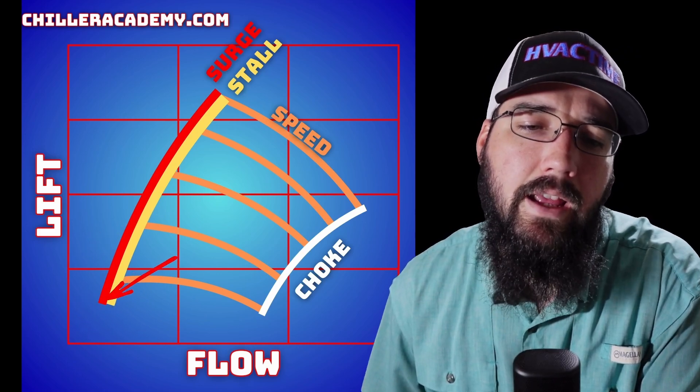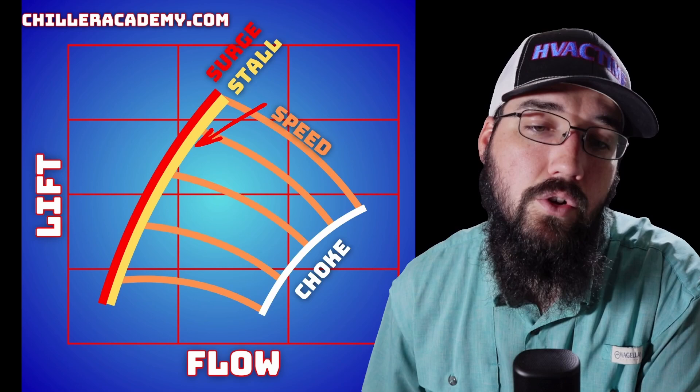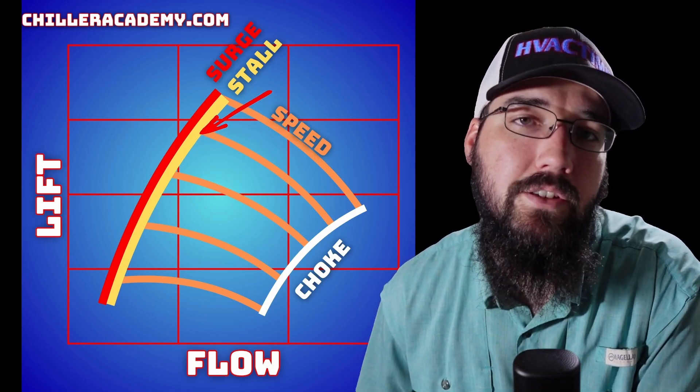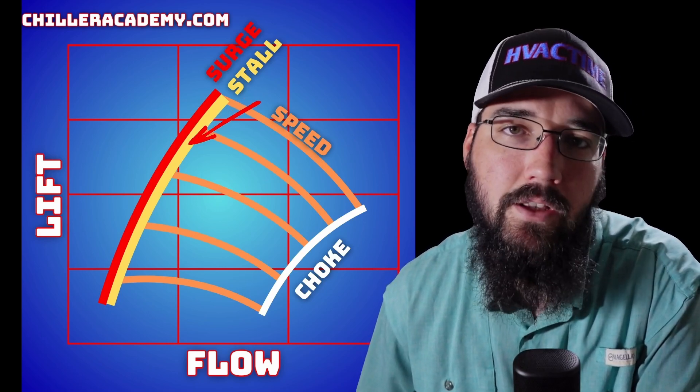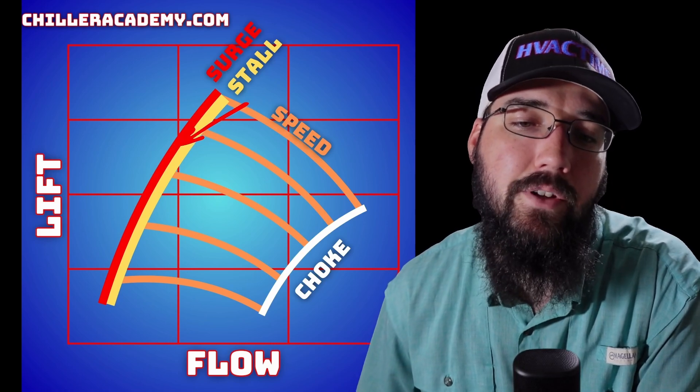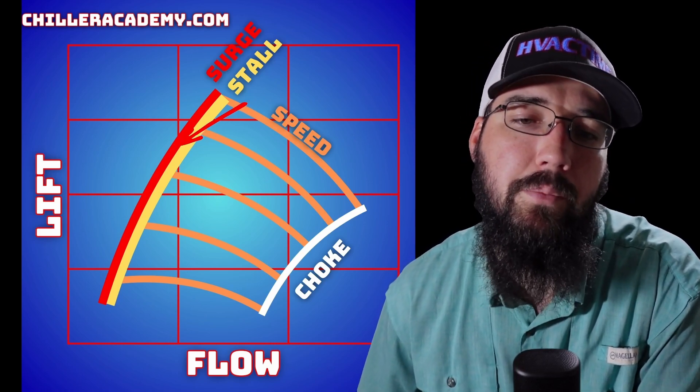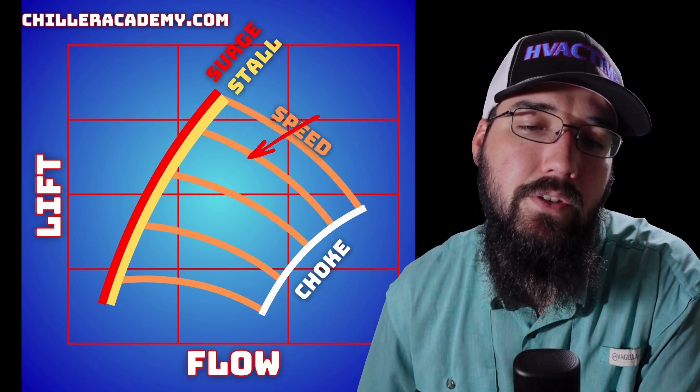Stall precedes a surge. When you get into an early unstable condition just before surge happens, this will typically sound like a low-end grumble or growl from the compressor. Then you'll get a high-pitched screeching or squealing type of noise from the compressor once you move into a surge. The speed of the compressor plays a heavy factor.